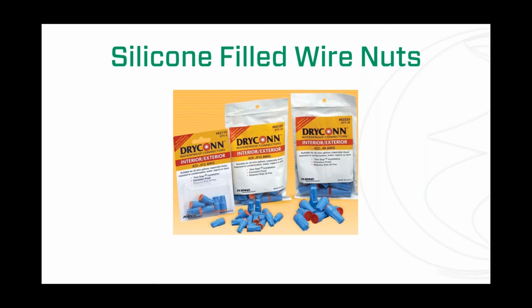I learned that it's not so much about keeping the moisture out of the actual connection, because if you've got moisture or water in there, it's probably wicking down your cords, and your electrical connection's probably not your biggest concern. But at some point, you're going to find that you're going to have gases, sewer gases in these pits. And those sewer gases can get into these junction boxes. And that's probably the biggest advantage I saw to silicone filled wire nuts, is that they can help keep your connection clean. I don't know if you're familiar with a wire nut, but a typical wire nut has like a little spring in it, and you have two pieces typically of copper wire that you put together, and you twist that little wire nut or that spring over them, and it makes a good tight connection that can last for a long time.